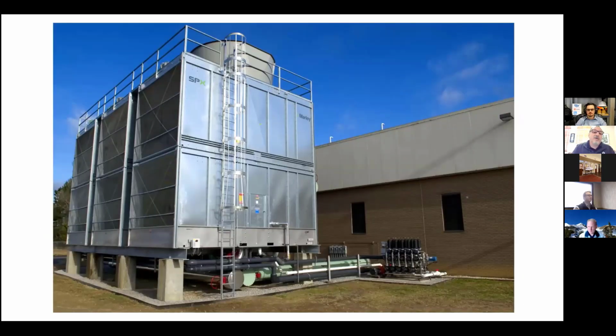This is an example of isolation. We did talk about in the last slide about taking it off of the sump. In this case, there's 3 towers right there, 3 beautiful Marley towers, and they're taking it off the equalizer piping. So it's very simple to pull off that equalizer piping, then pump it on back through probably a series of sweeper systems in each tower. And then we recommend putting isolation valves on each sweeper system of the tower.